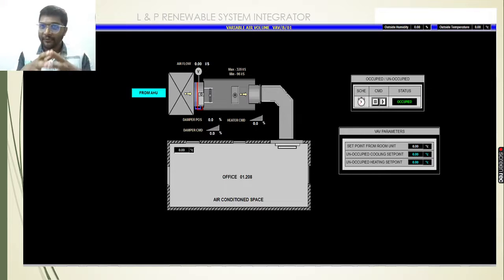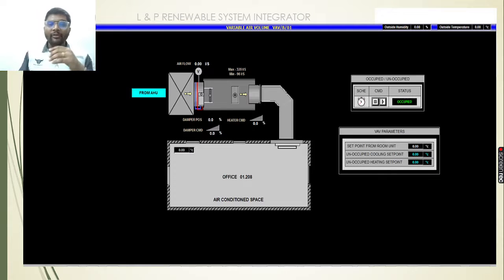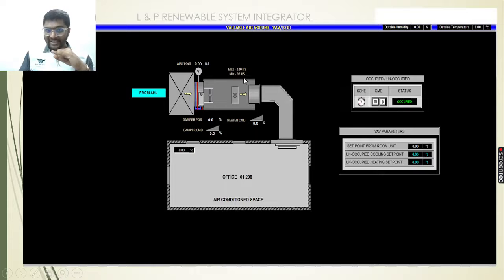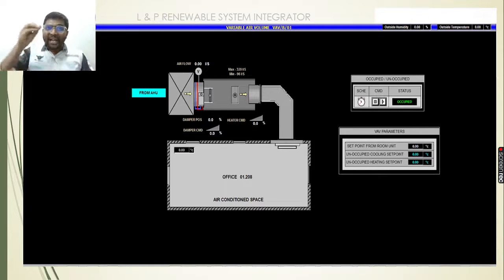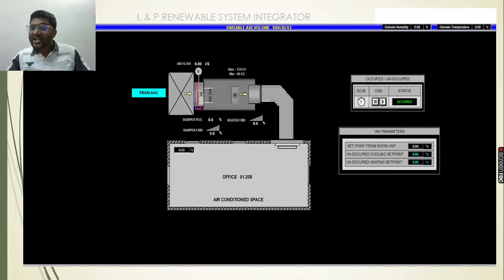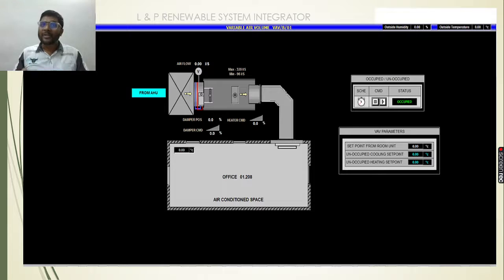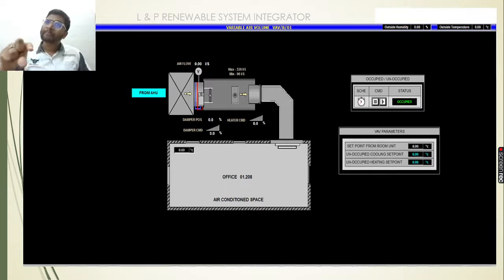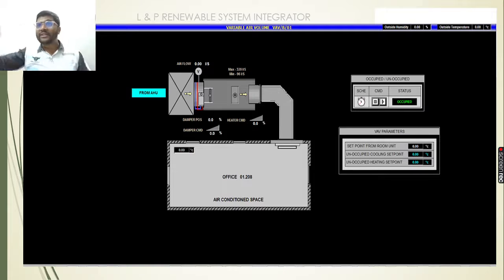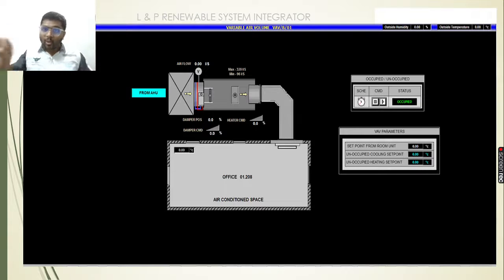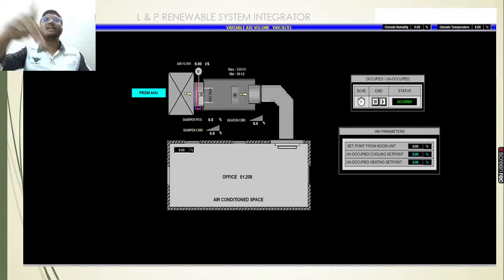Air balancing is the most important step. When you do air balancing, you can determine the minimum air flow in liters per second and the maximum air flow in liters per second for a particular room or environment. With the minimum flow you can calculate the minimum voltage required to operate the damper. Once air balancing is done, we fix the damper at the V-minimum position for minimum flow and at the V-maximum position for maximum air flow. After setting the set point, the control will operate only between these V-minimum and V-maximum values.